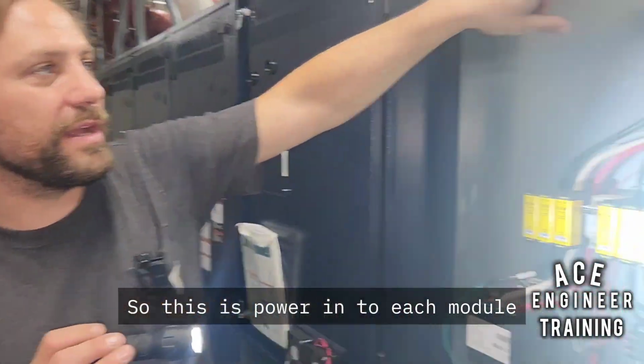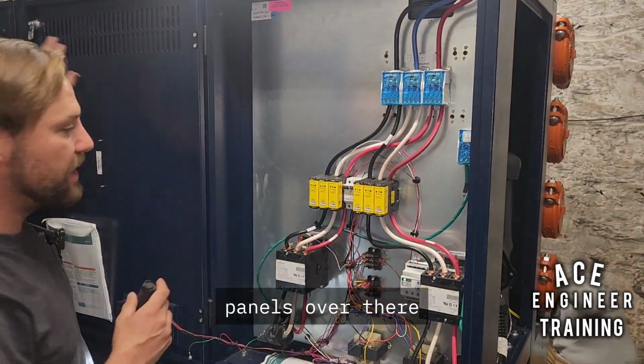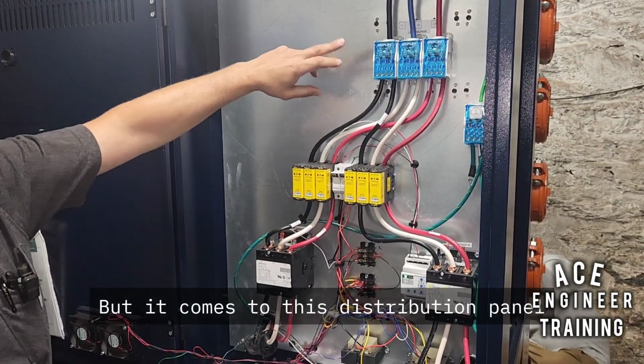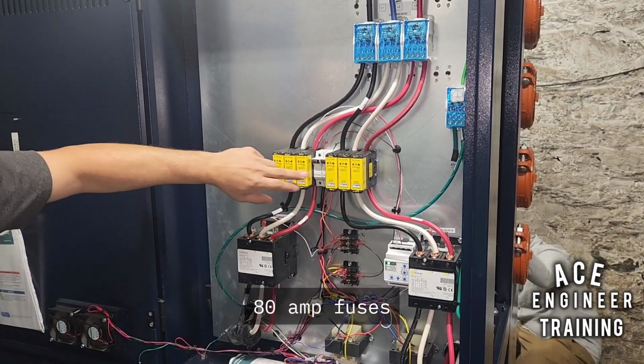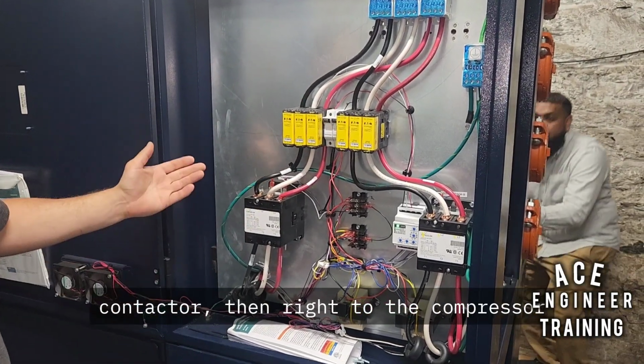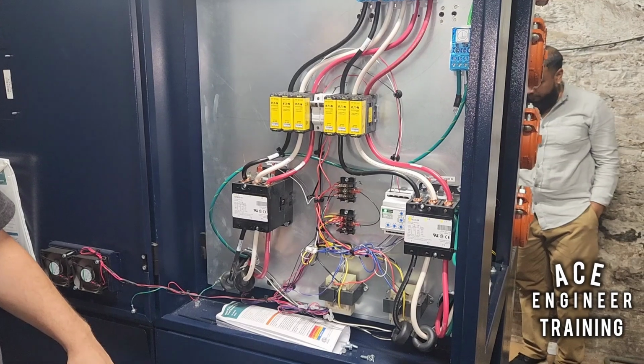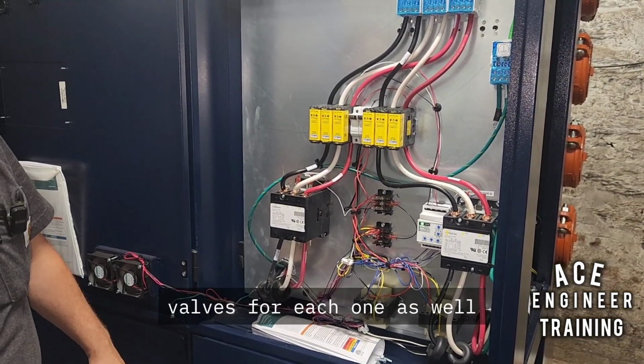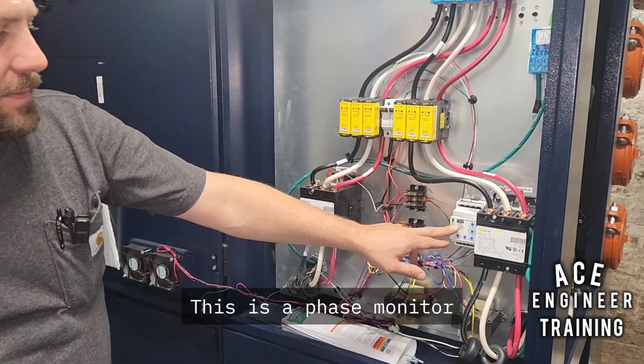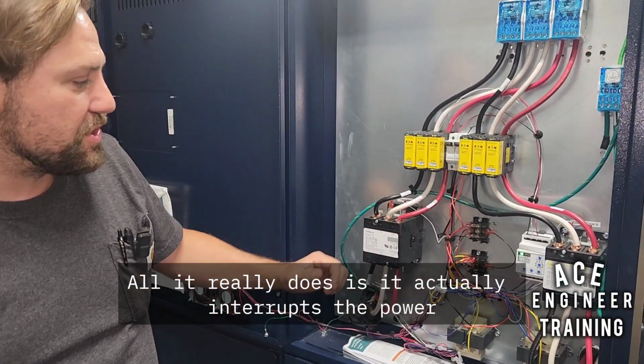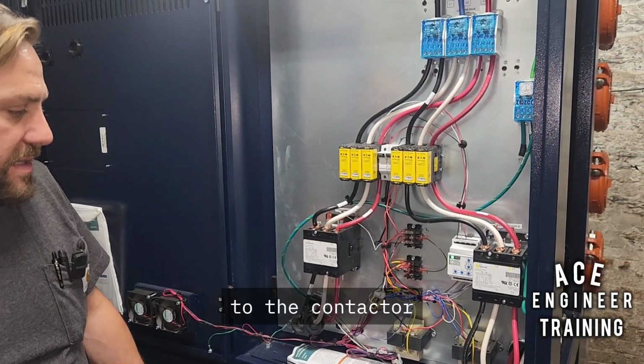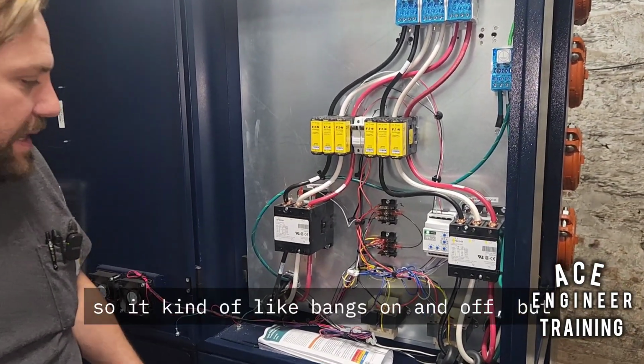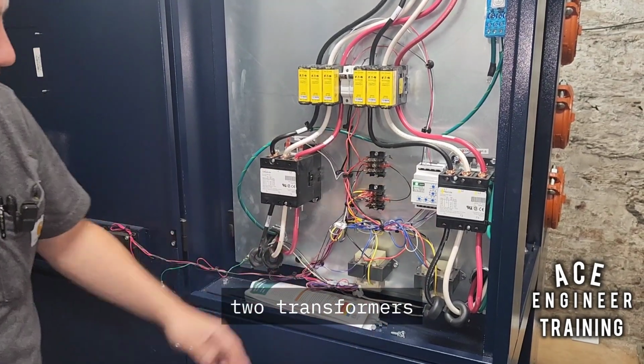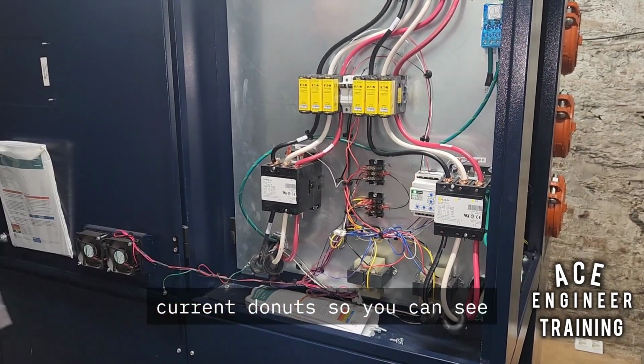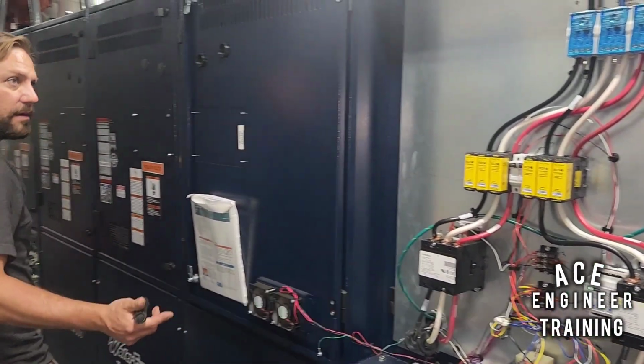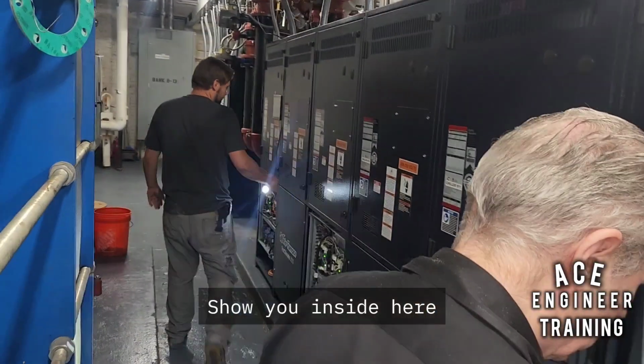So this is power into each module. They all have their own disconnects in those panels over there, and they're marked, right? But it comes to this distribution panel, into these fuses, 80 amp fuses, contactor, then right to the compressor, regular scroll on-off compressor. They actually have electronic expansion valves for each one as well. It's a phase monitor. All it really does is it actually interrupts the power to the contactor, so it kind of bangs on and off. But 2 transformers, current donuts, so you can see. But pretty much it. You have these fans here. I'll show you inside here.